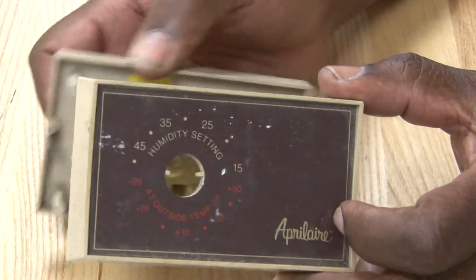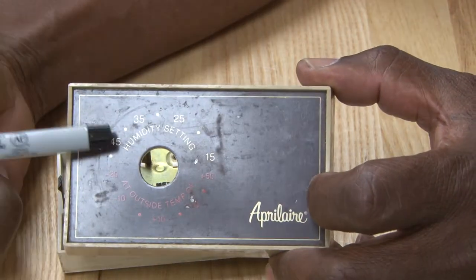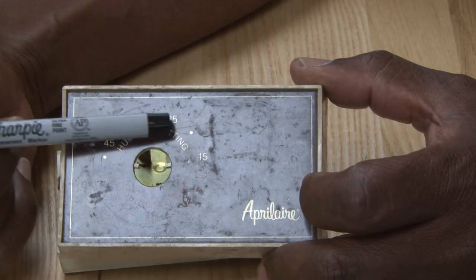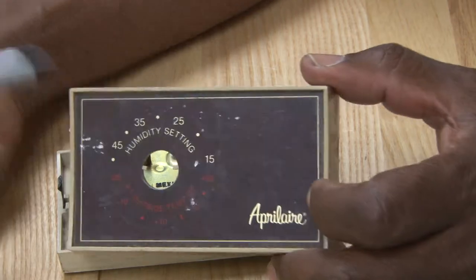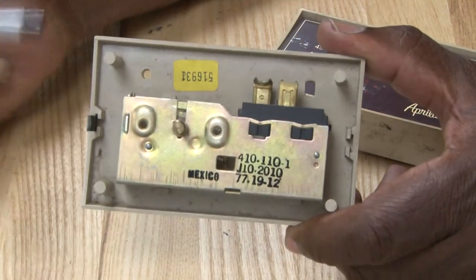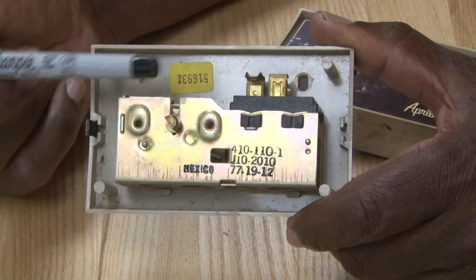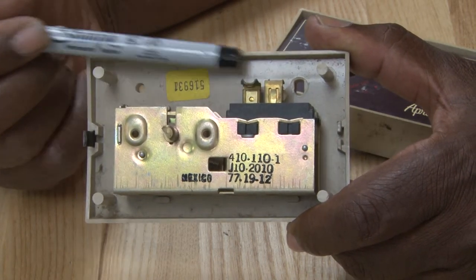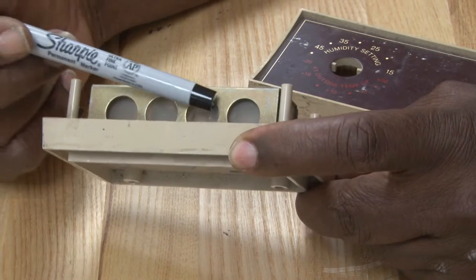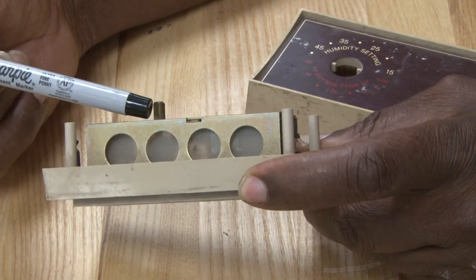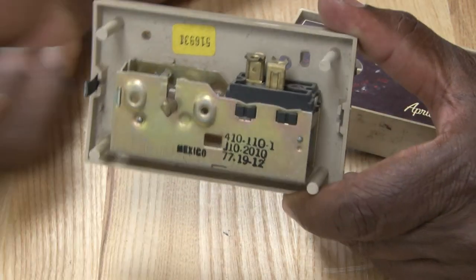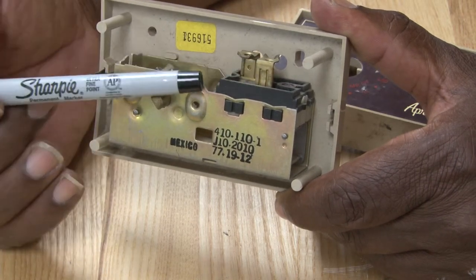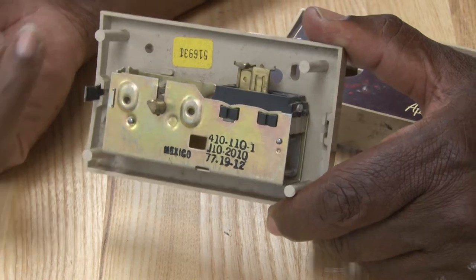Another type of control that we may find is what we call a humidistat. This humidistat, if you notice, will sense the percentage of moisture in the air, and you'll be able to adjust it by the knob that would fit onto this shaft. This is the internal part, and the wires for your humidistat would connect here. And basically, there's a special material on the inside of it that will expand or contract based on the amount of humidity in the air. And so it will open and close the switch to turn, like I said, your humidifier on and off. This is another type of control that will operate in the house for your humidity.